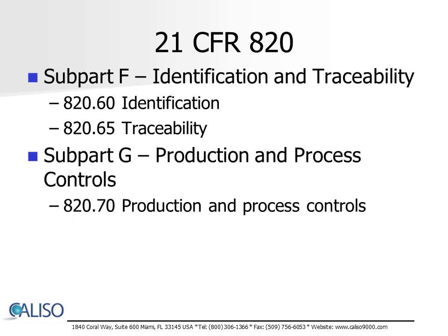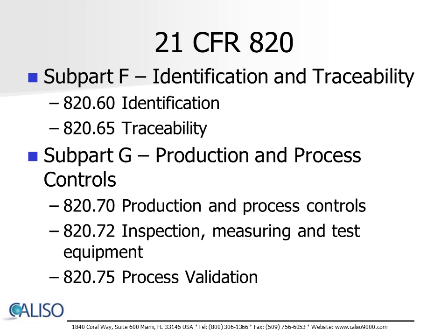Subpart G, Production and Process Controls. This is also a quite detailed section, and includes requirements for control of production and process changes, environmental control if the environment can adversely affect the product, personnel hygiene requirements, building suitability, and maintenance of machinery. Subpart G also contains requirements for inspection, measuring, and test equipment, also known as calibration, and process validation.